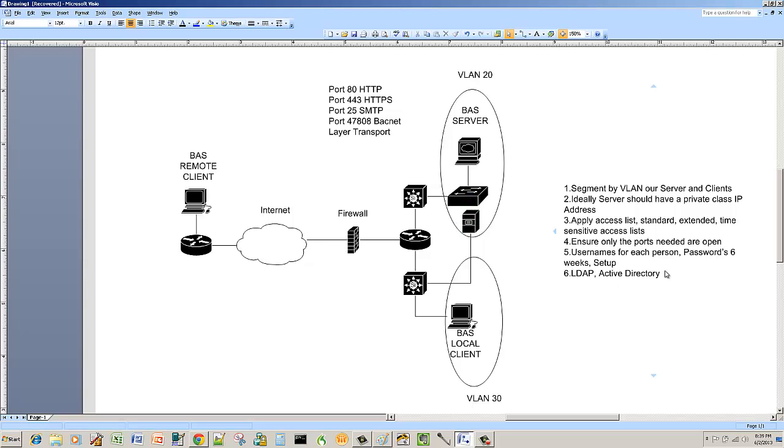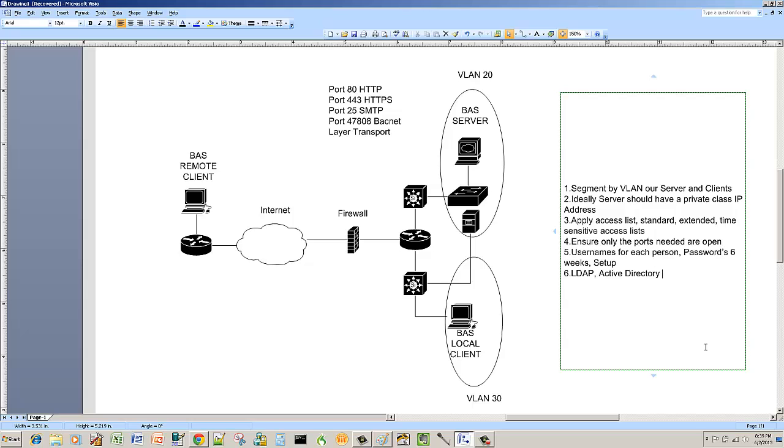And I work with IT and I say, hey, here's my system. I want to, one, set up my supervisory devices to be monitored, and granted that's the next point I'm going to make, but I want them monitored, but also I want everyone's username and password to be set up in Active Directory, so that way I can force password resets, I can monitor people who try to log in too many times, I can flag them, I can set up group policies, rules. It just makes it really nice. So Active Directory whenever possible.